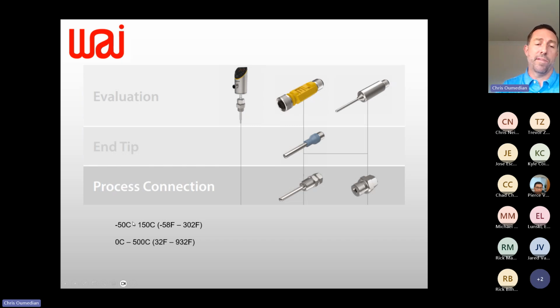You'll look at the measurement ranges down below, and these are specific to our products. On the base devices, our standard devices, if you look at our portfolio, 80% of our offering is negative 50C to 150C, which equates to negative 58F and 302F, which is fitting for a lot of industrial applications, a lot of process applications. You get into some applications with furnaces, heating, molten metal, that sort of stuff. With these devices, we can go from 0C up to 500C, which is 932F, which is, I don't know how many of you have seen applications above 1,000 degrees Fahrenheit. They do exist. We'll talk about another technology in a minute, thermocouple, which can get you well above that. So we've got a host of products that should be able to suit most applications.